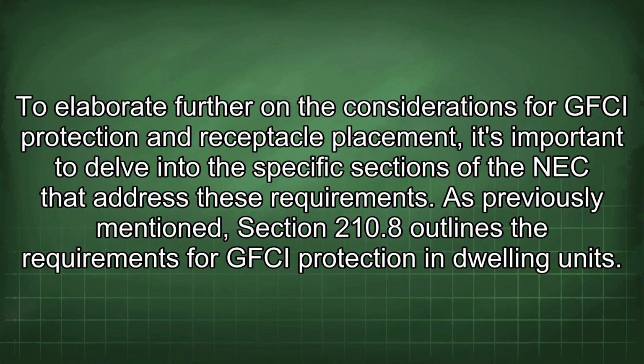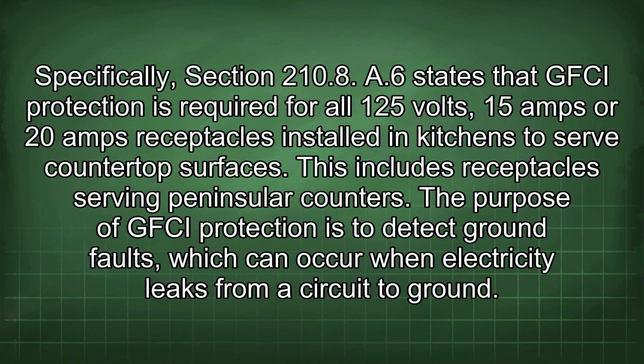To elaborate further on the considerations for GFCI protection and receptacle placement, it's important to delve into the specific sections of the NEC that address these requirements. As previously mentioned, Section 210.8 outlines the requirements for GFCI protection in dwelling units. Specifically, Section 210.8.A.6 states that GFCI protection is required for all 125 volt, 15 amp or 20 amp receptacles installed in kitchens to serve countertop surfaces. This includes receptacles serving peninsular counters.